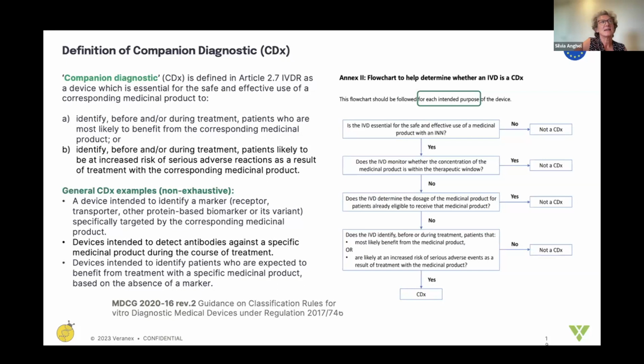Now, CDx are classified based on their intended purpose. It means that an in vitro diagnostic device, in order to be classified as a companion diagnostic, must be considered, as in the United States, essential for the safe and effective use of the corresponding medicinal product. A good flow chart allowing the determination of the classification of an IVD as a companion diagnostic is given by the MDCG guidance 2020-16 revision 2. Very important, since in revision 1 we didn't have this flow chart.